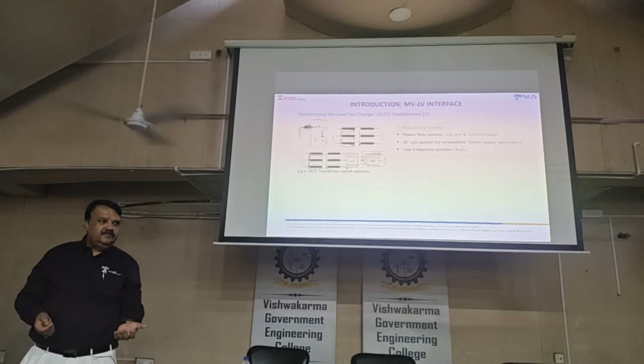Why should I have the substation at the ground? Because of the bulky transformer, switchgear, everything. If I can shrink the size and weight to a lower value, I sell this land to a property owner. He will build a 100-story building and give me $5 million, let's say. Then this substation, if it is lighter, we can take to the top of the building. So each building can have a substation, and the land becomes free for other purposes.